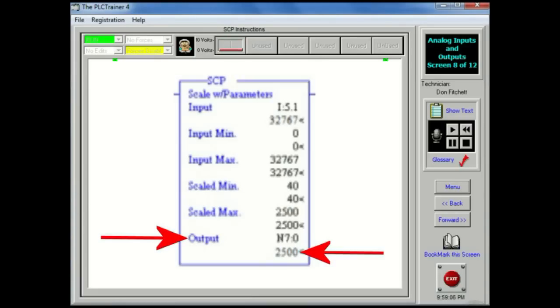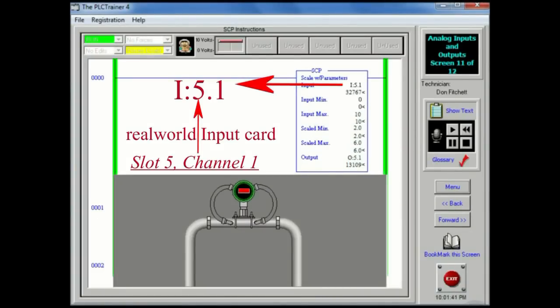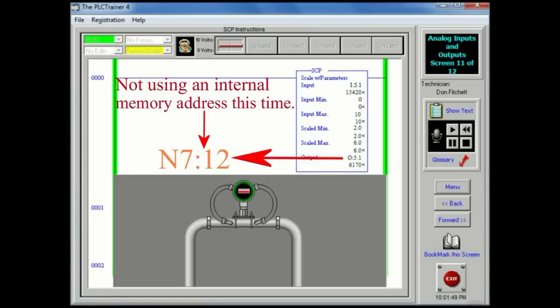If any floating point file types or floating point constants are encountered in any of the previously described parameters, the entire instruction is treated as floating point and all immediate integer values are converted to immediate floating point data values. The function of the SCP instruction here is exactly the same as described previously. The exception being that the output word that is specified is an analog output address rather than an integer word address.